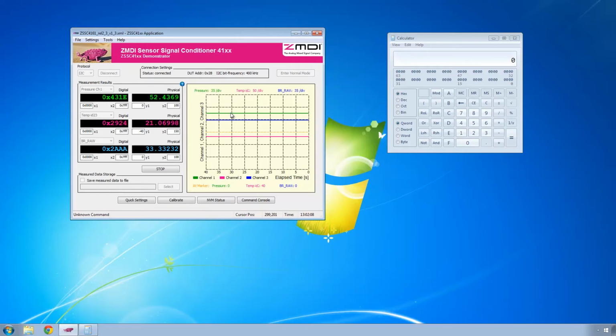You can also see that I'm actually running the software now. So if I adjust the potentiometer for the pressure sensor, you can see in green the calibrated measurement, and in blue the raw measurement, adjusting up and down.